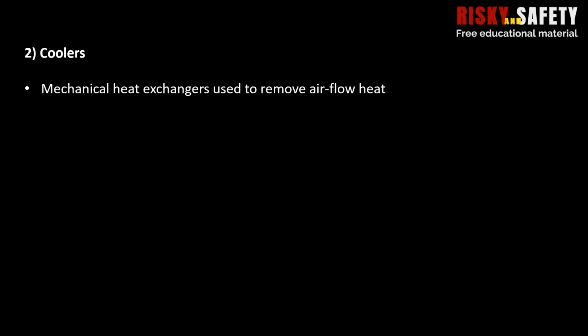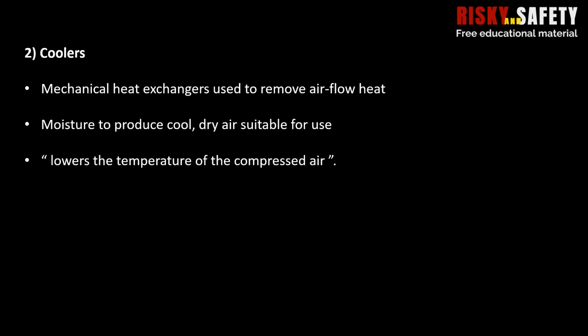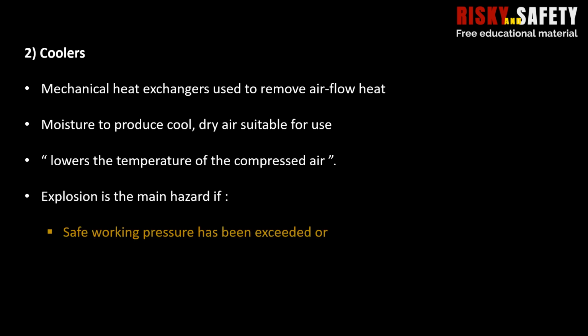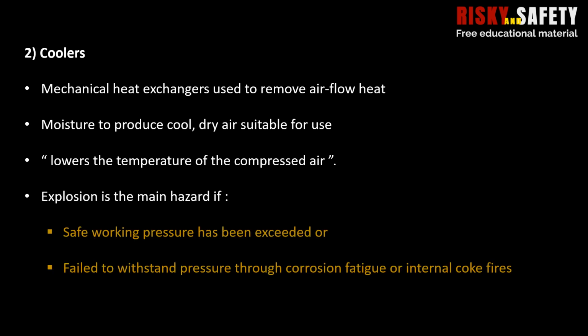Coolers. Mechanical heat exchangers used to remove airflow heat and moisture to produce suitably cool and dry air for use in air-powered equipment. Many aftercoolers are pressure vessels and the associated hazards are similar to those of air receivers. So explosion is the main hazard if the safe working pressure has been exceeded, or because of failure to withstand pressure through corrosion, fatigue or internal coke fires.